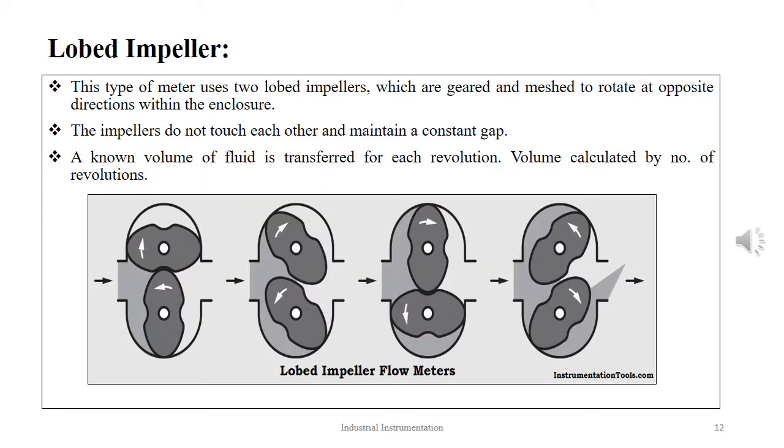The next type of positive displacement flow meter is the lobed impeller. This type of meter uses two lobed impellers which are geared and meshed to rotate at opposite directions within the enclosure. Two rotating impellers with cross-sections rotate in opposite directions due to the gas flowing through and the force being exerted by that. The impellers are shaped such that the gap between them remains constant without getting touched. A gear arrangement assures the synchronous movement of the impellers using adjustable fine-tuned gear train arrangement.